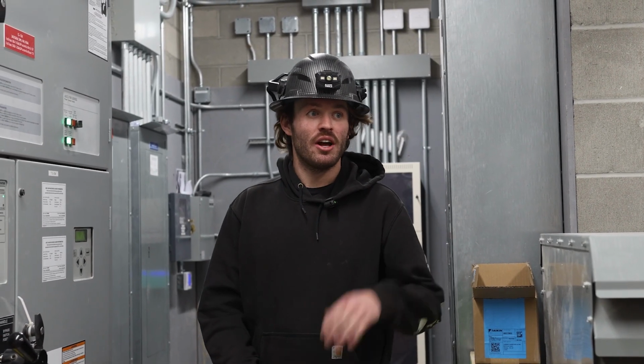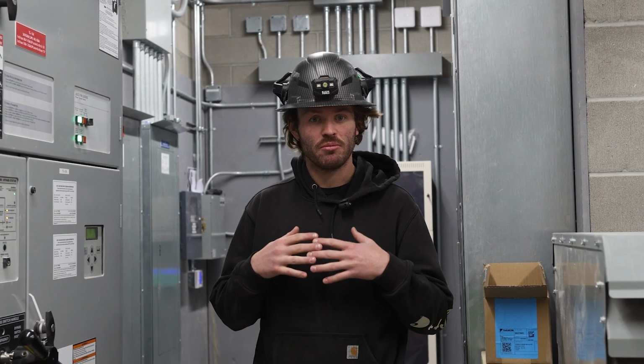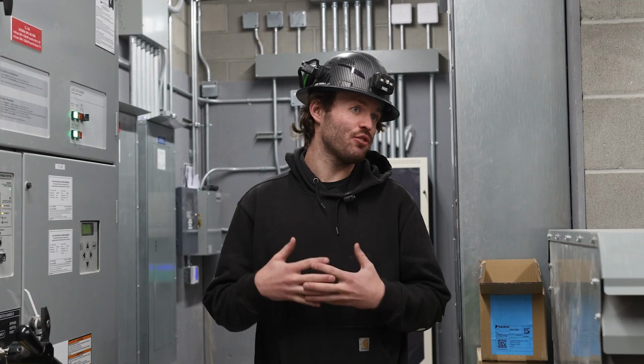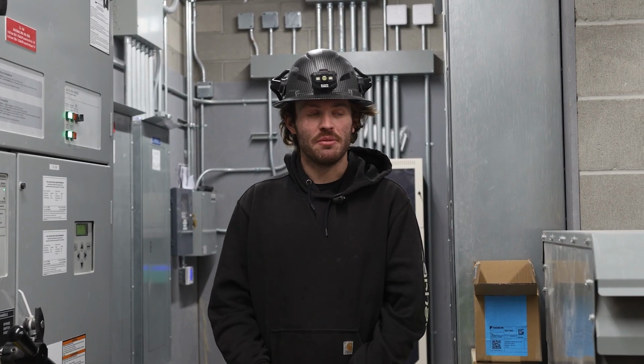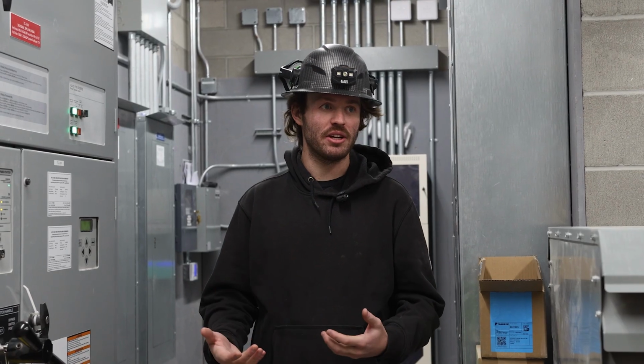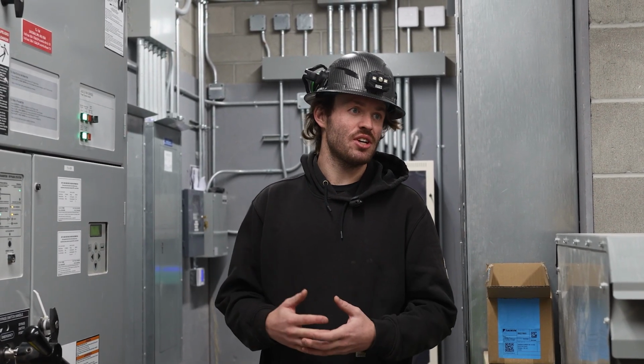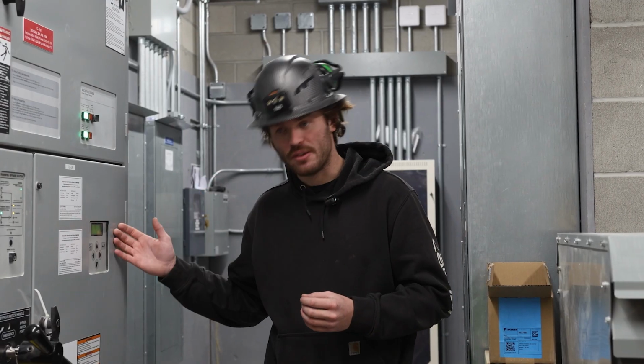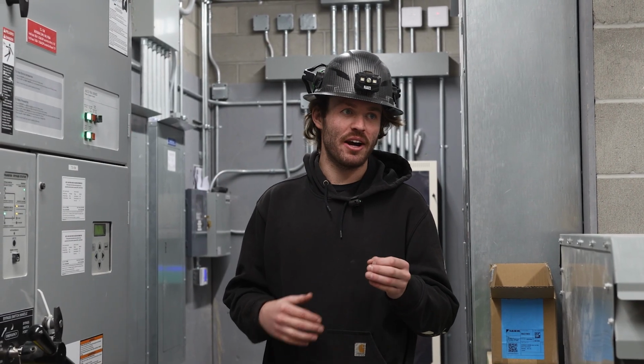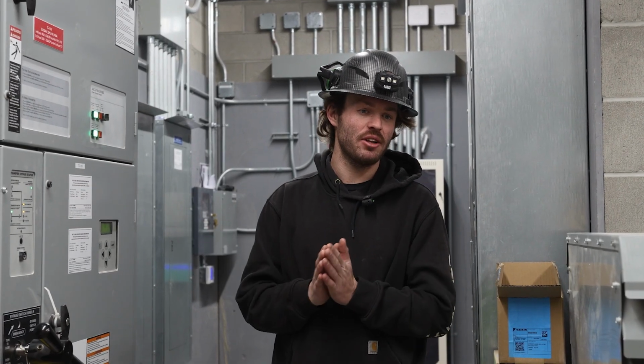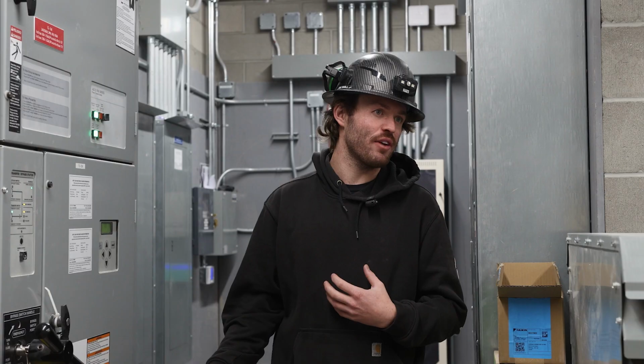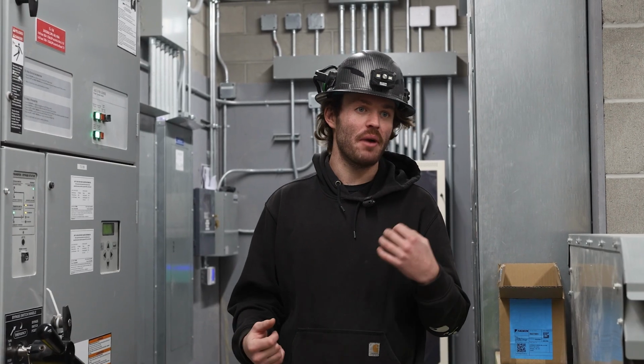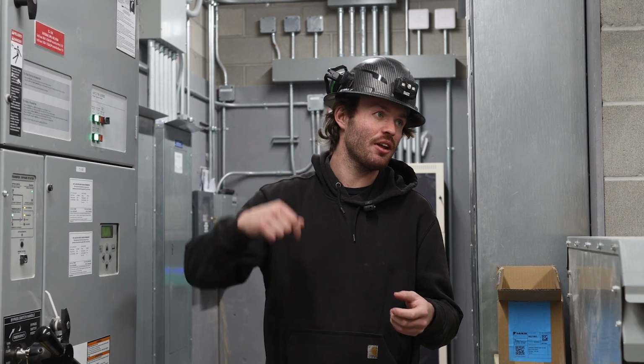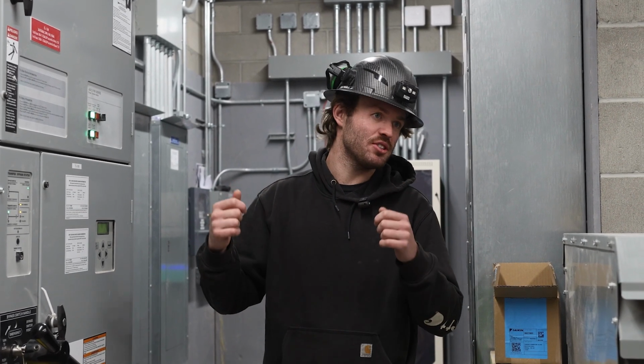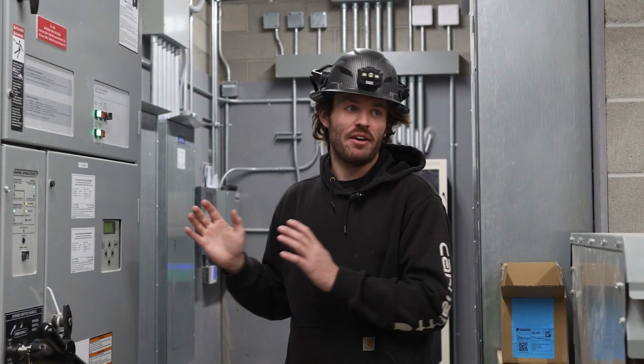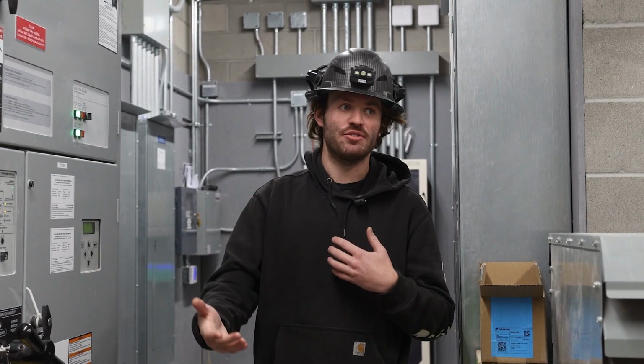Once it sees our generator voltage as accepted, so in a stable, good range, it will then automatically transfer to the generator itself. Once utility power is stabilized or returns, if it was a complete outage, it will start a process of transferring back to utility power. As soon as utility power comes back on, it will not transfer right away. We have a time delay in there to prevent unnecessary transfers and interruptions. So a common thing: Manitoba Hydro fixes whatever took out their power line, they flip the fuses back in, and it pops instantly because there's another fault down the line. That's why we have that time delay. It prevents unnecessarily transferring back and forth.